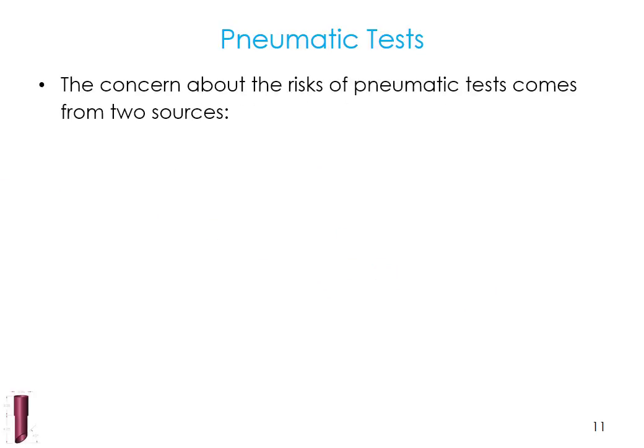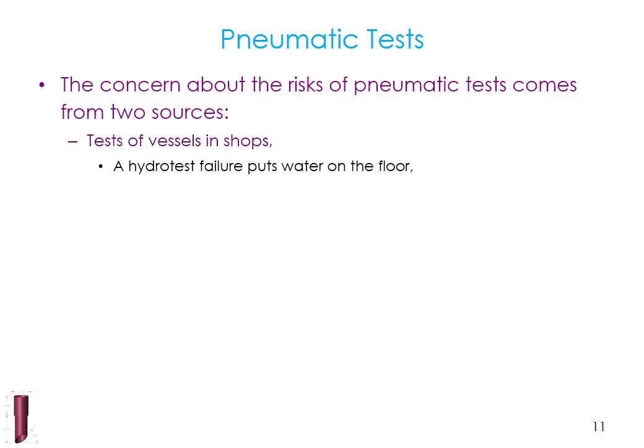The concern about the risk of pneumatic tests comes from two sources. Tests of vessels in shops. A hydrostatic test failure puts water on the floor. Kind of messy, no big deal. A pneumatic test failure puts shrapnel through the wall. That's a big deal.